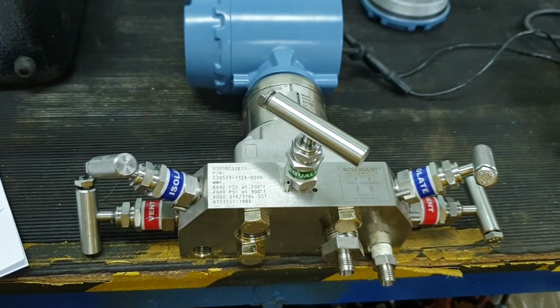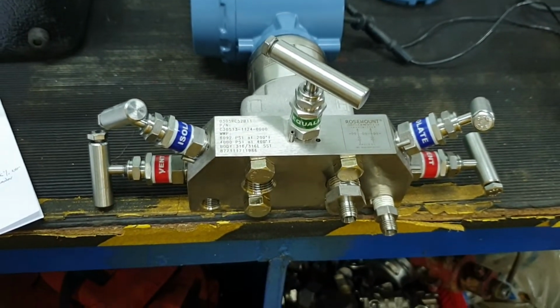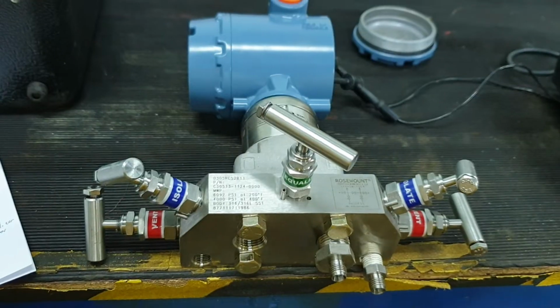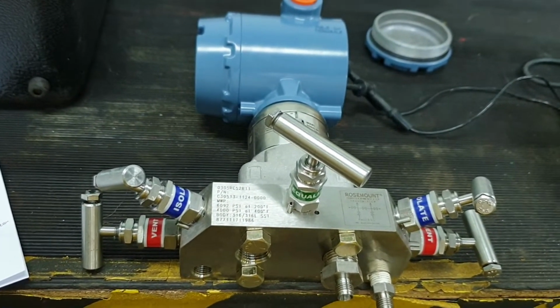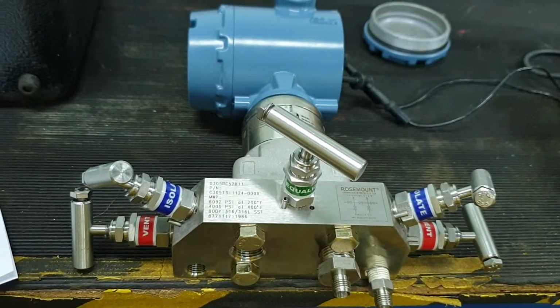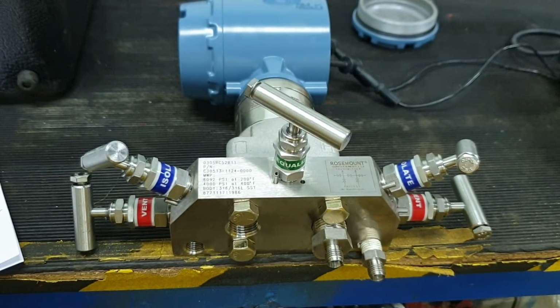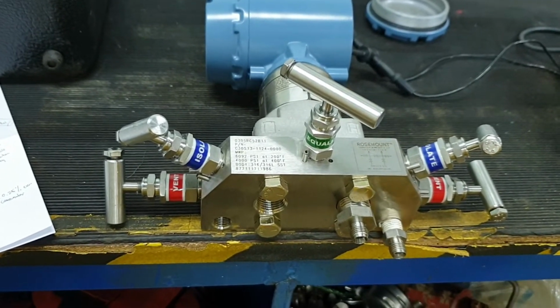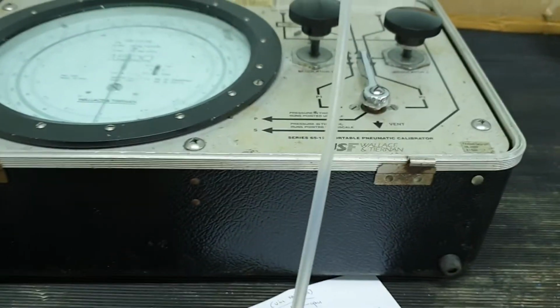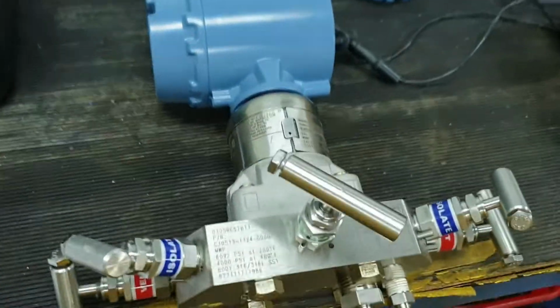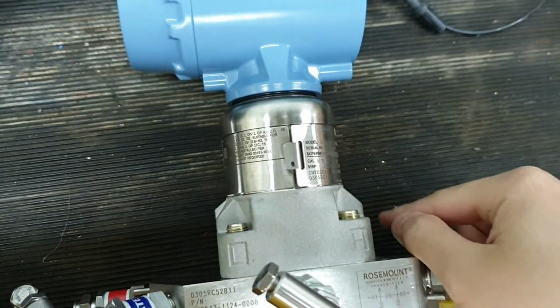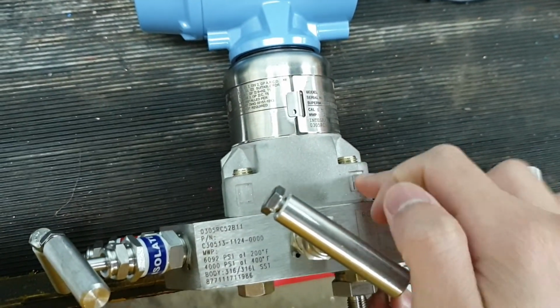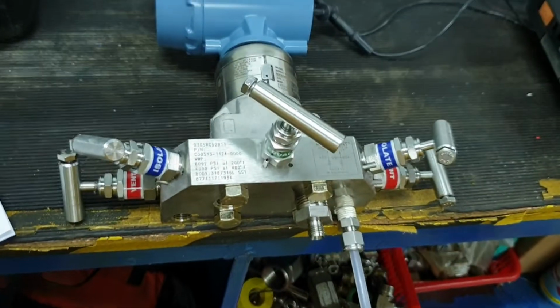Once we have fully closed the equalize valve, we will connect the calibrator. I forgot to mention, one of the reasons that we fully close the equalize valve is to confirm that the reading is 0. Next, we will connect the instrument line from this calibrator into the transmitter vent line at the high pressure side. As you can see here, we have the high side and the low side. For testing purposes, we will connect it to the high side. All right.